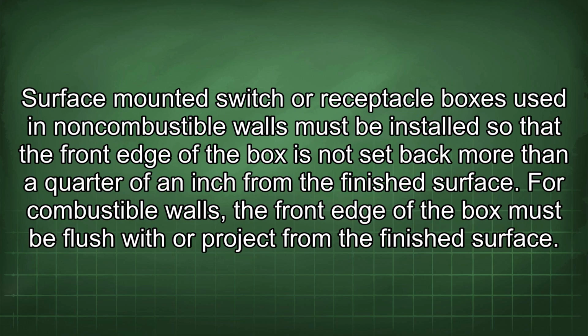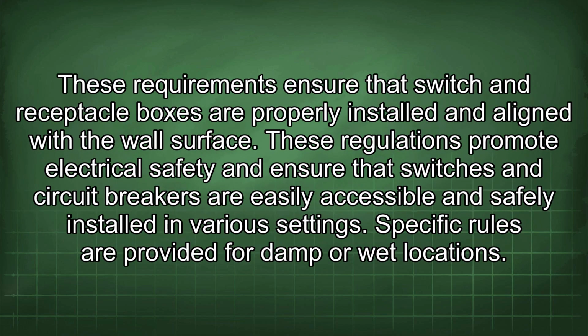Surface-mounted switch or receptacle boxes used in noncombustible walls must be installed so that the front edge of the box is not set back more than 1/4 of an inch from the finished surface. For combustible walls, the front edge of the box must be flush with or project from the finished surface. These requirements ensure that switch and receptacle boxes are properly installed and aligned with the wall surface. These regulations promote electrical safety and ensure that switches and circuit breakers are easily accessible and safely installed in various settings. Specific rules are provided for damp or wet locations.